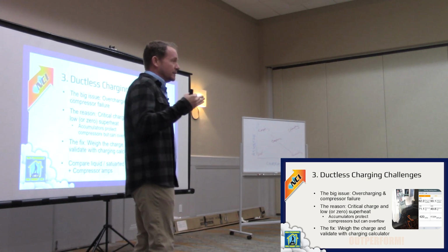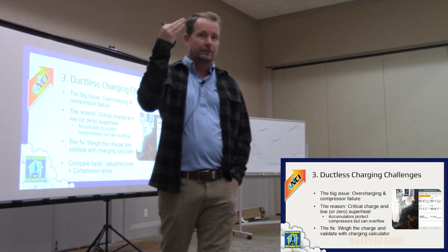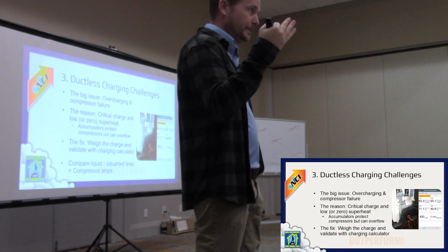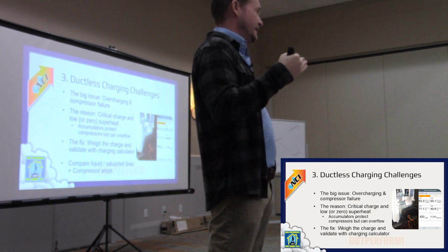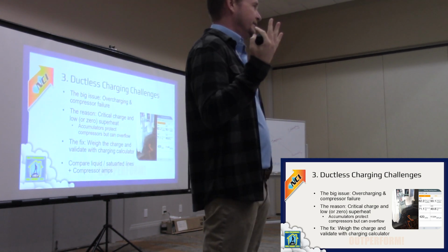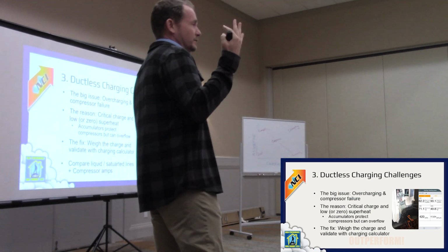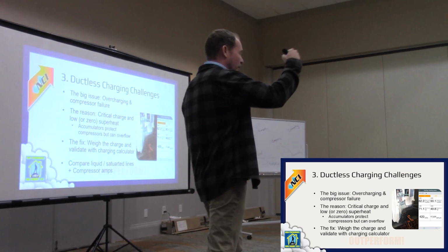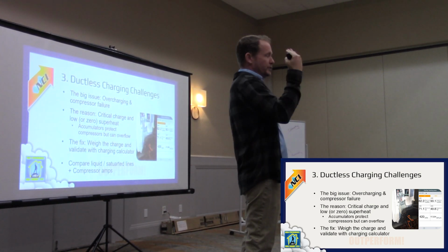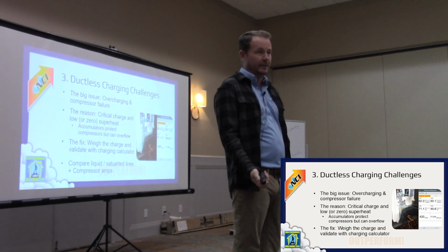One nice thing about ductless manufacturers is they generally give you pretty good airflow charts, telling you your airflow at different speeds, and they're usually pretty accurate, at least the ones I've tested. There are probably some out there that don't at all. But if you go off the manufacturer's airflow, once you have airflow, doing delivered capacity is really easy.